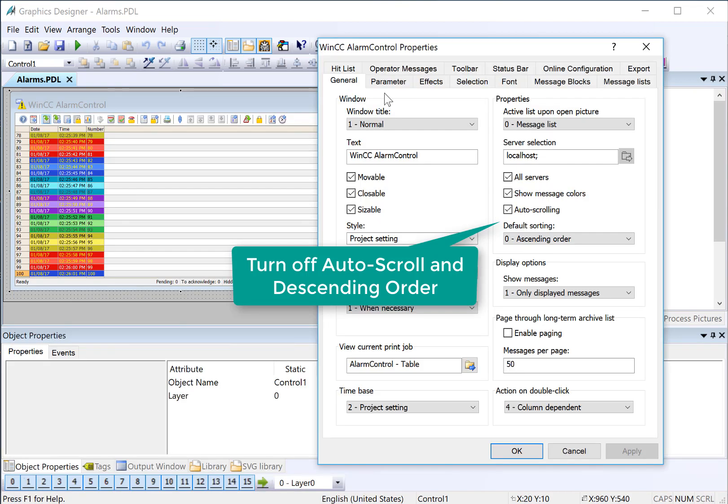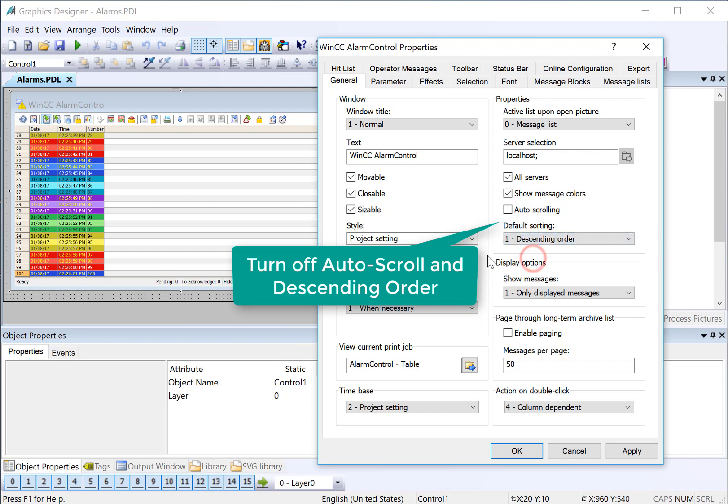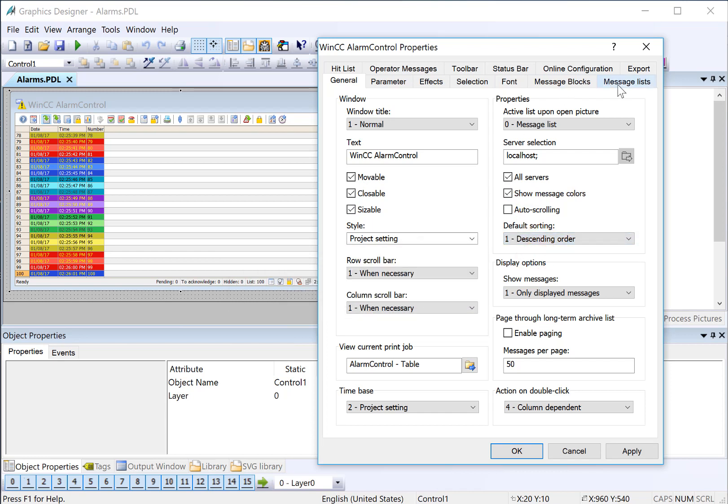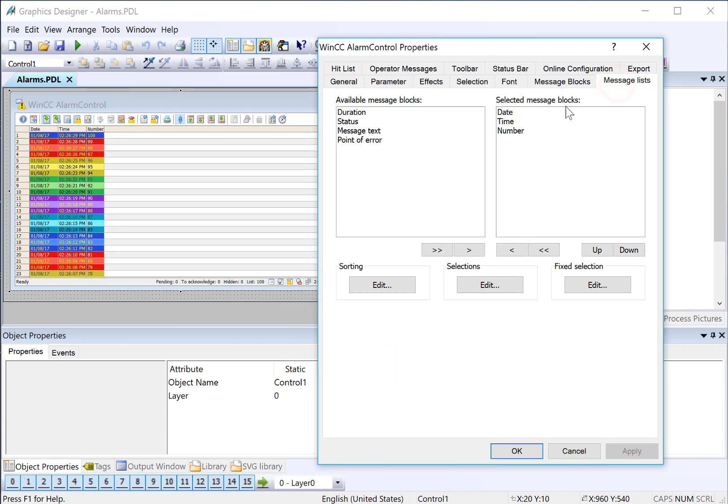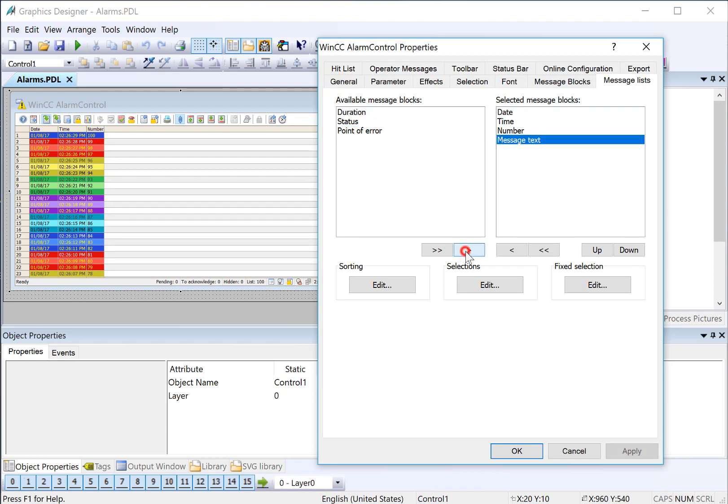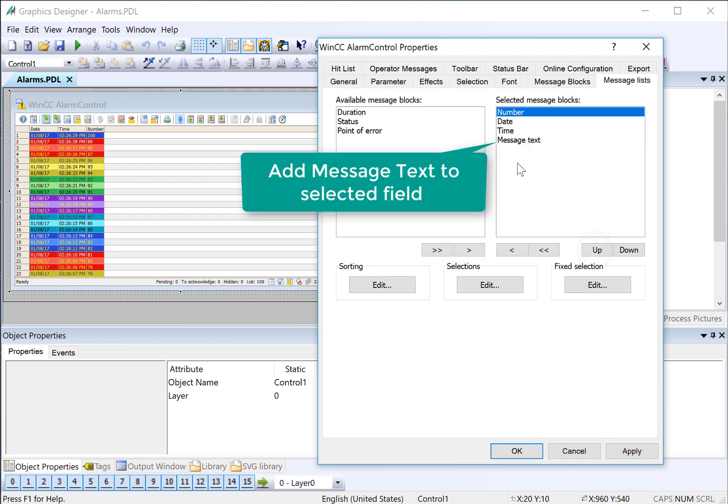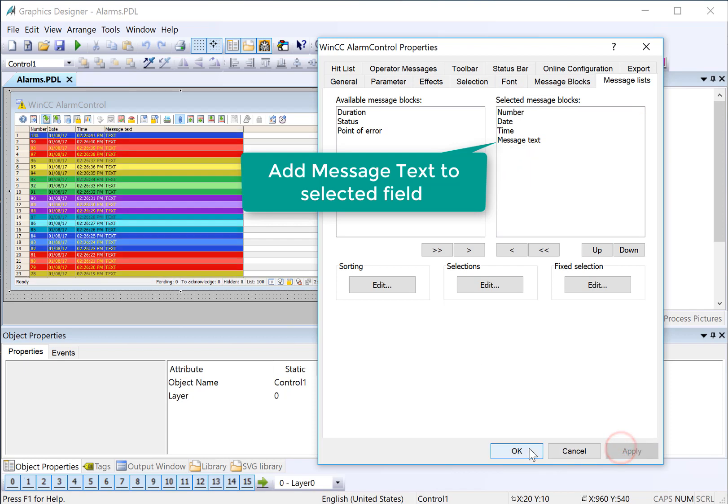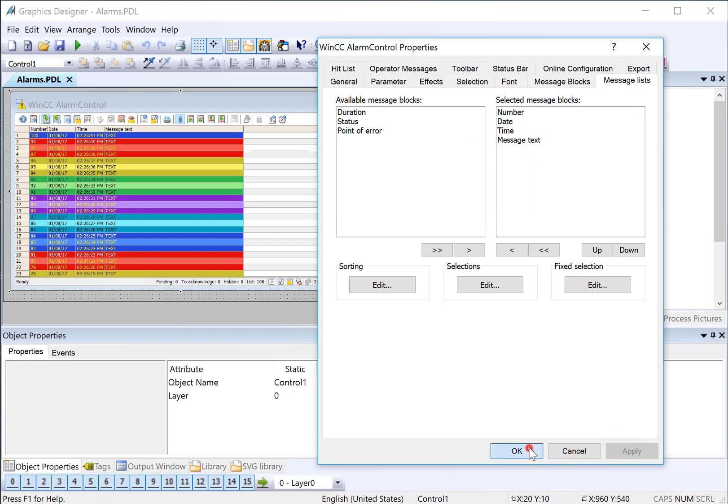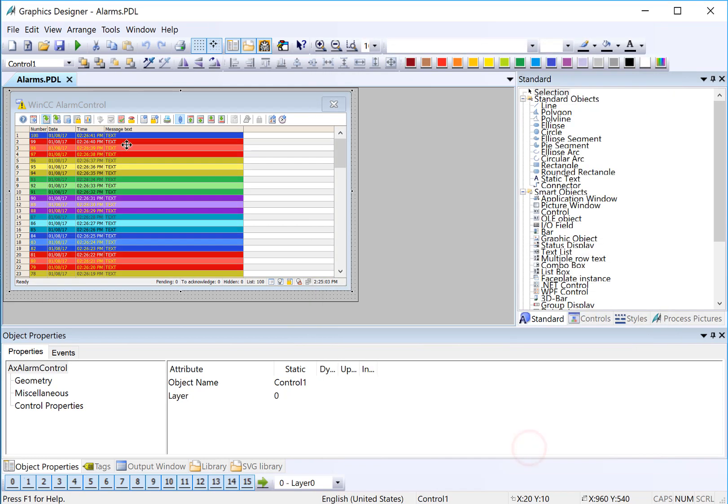On our alarm screen, we're going to configure our alarm control. I'll double-click. And on the General tab, let's turn off auto-scrolling and set it to descending order. On our message lists, we will add our message text and set our number as the first block. And I'll just click Apply and OK. You can see it reformats our alarm control, and it gives us more room on our message text. This is because we set the width to 60.